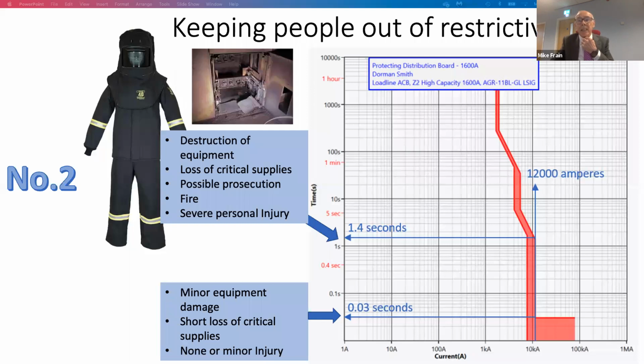We're looking at an arcing fault there of 12,000 amps. And if you can see the instantaneous pickup level there, where it coincides with that, you can see that it could trip in 30 milliseconds at the bottom, or just for an amp or two more, it could be tripping at 1.4 seconds. So what's the difference? Well, if it trips at 1.4 seconds, we're talking about destruction of equipment.